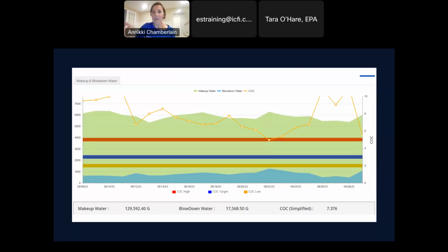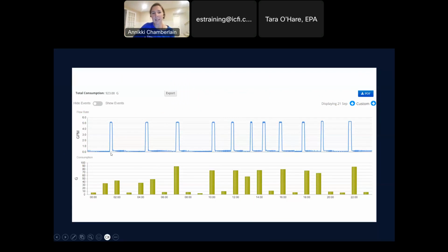Here's the opposite. This is probably a scale event, right? My cycles is too high. Again, I can see my high threshold is 5, but I'm pretty much running above that all the time, basically a cycles of 7. So we don't want water waste, but we don't want scale, right? We in fact probably want scale less than we want water waste because it's much more expensive and damaging. So again, I'm going to go in and look at my high resolution. And I can see my blowdown is working, but it doesn't have enough blowdown. So I'm going to verify it.